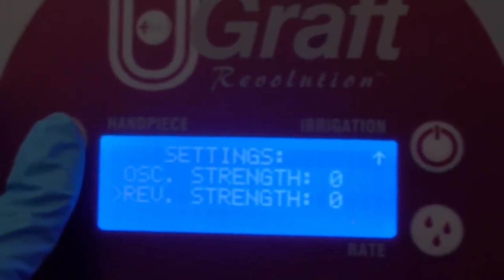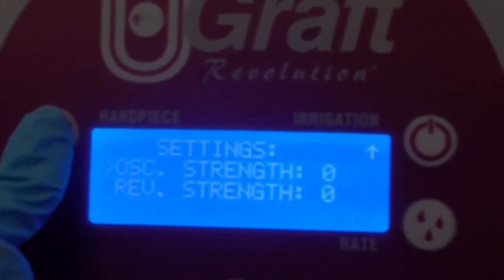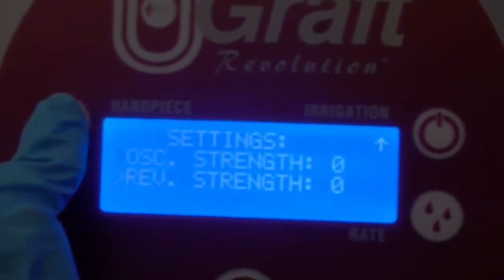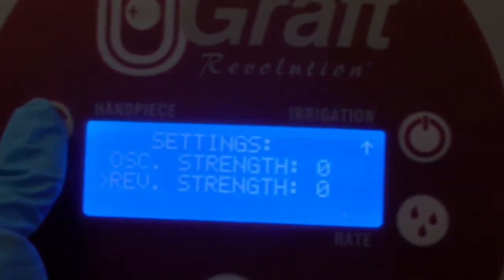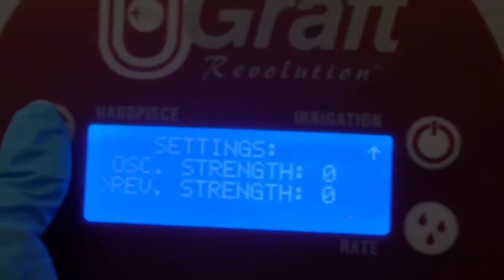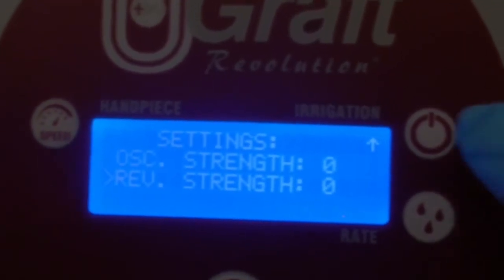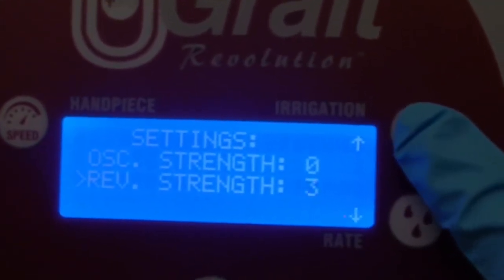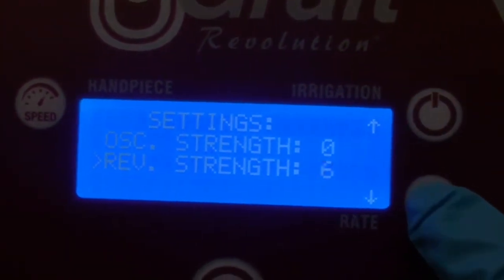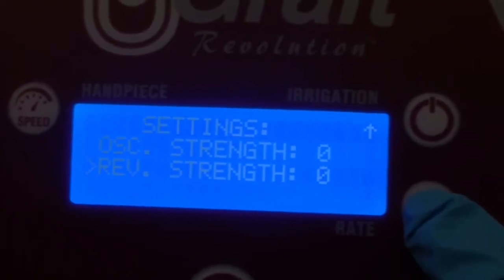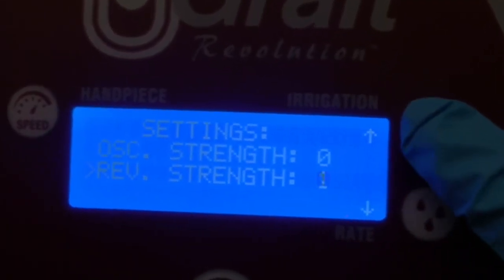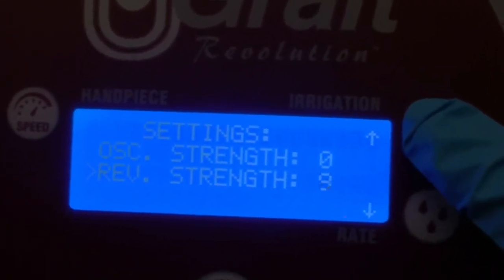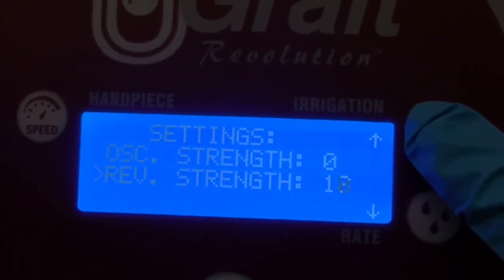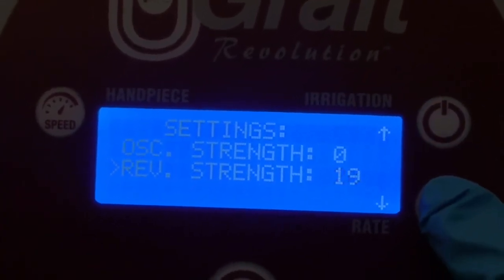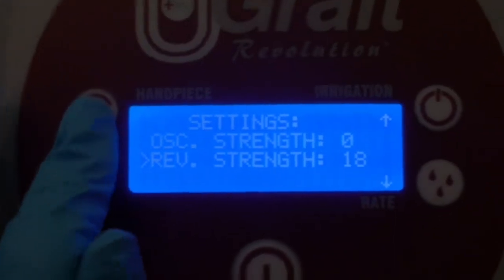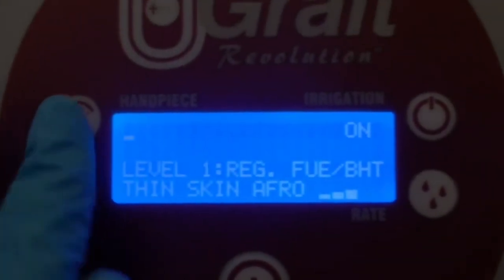You can adjust the strength for both revolution and oscillation. Pressing the speed button will allow you to toggle between revolution and oscillation strength. Use the buttons on the right adjacent to the arrows to increase or decrease the strength value as shown. The strength range is from 0 to 30 for both rotation and oscillation strength. To get out of the settings mode, press and hold the speed button for 2 to 3 seconds again.